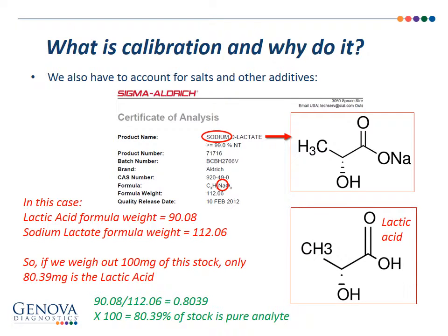So you just need to pay attention to this and make sure that you're accounting for these sorts of things. We try not to use salt forms if possible, just because it can have other impacts that you may not be thinking of. In this particular case, it's sodium, so this could have effects on the buffering capacity of your solutions, of your calibrators. There could be other issues down the road. It may not make a difference. So it's really just about making sure that we're documenting what we're doing, we're adjusting for any sort of impurities like this, and being aware of the potential ramifications.